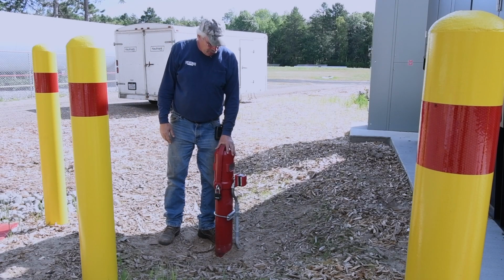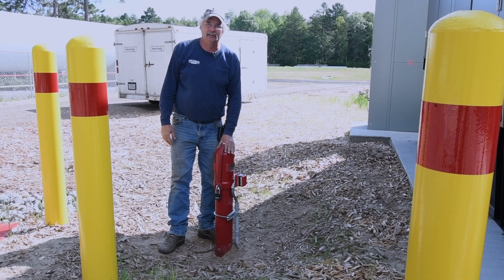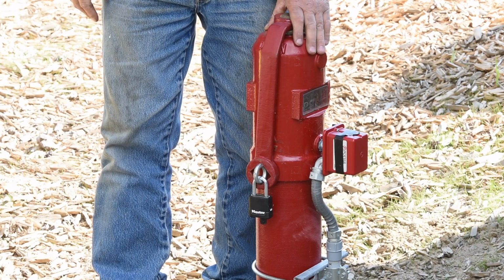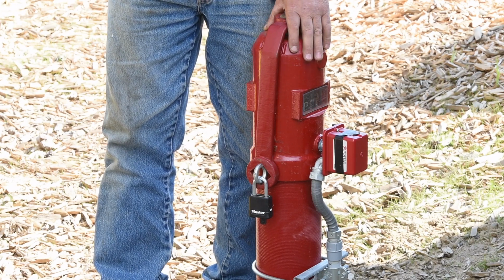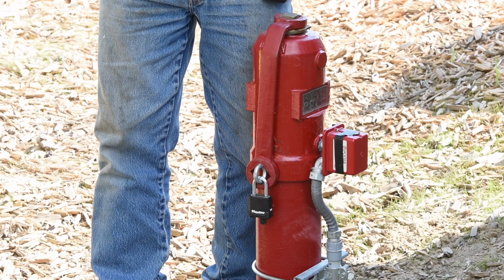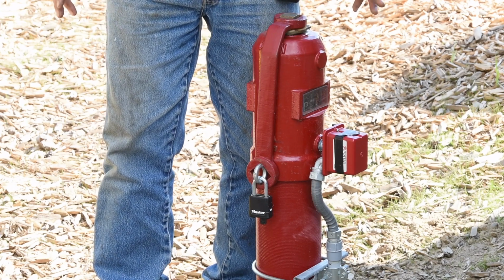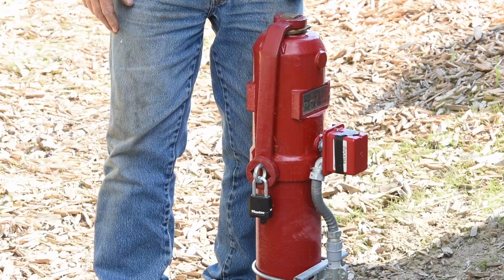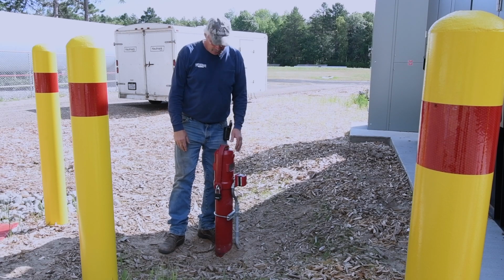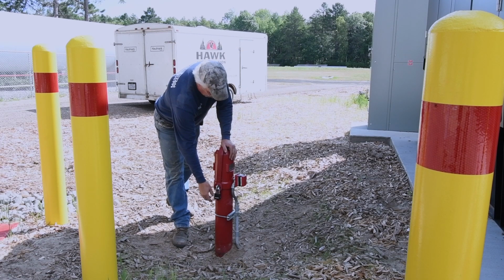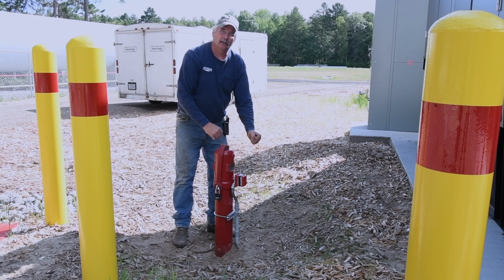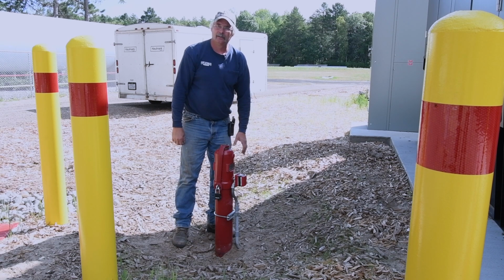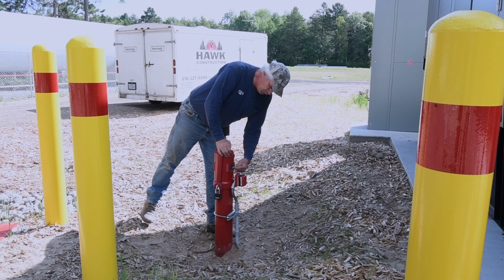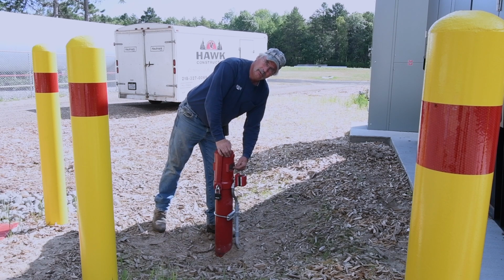This is a post indicator valve identified as a PIV, and what this is for is the lead in from the underground from the fire pump to the north end. So at any time that you'd ever want to shut that line off and shut both the systems off, unlock the lock, take the handle, put it on top, turn it to the right. It'll say open and closed right here on the side of the chamber.